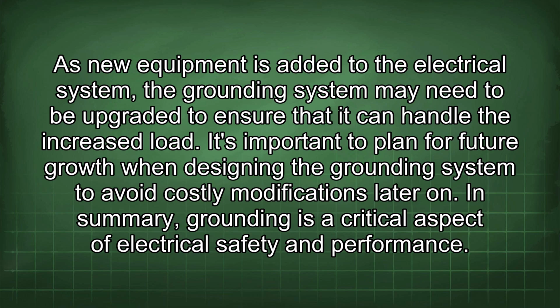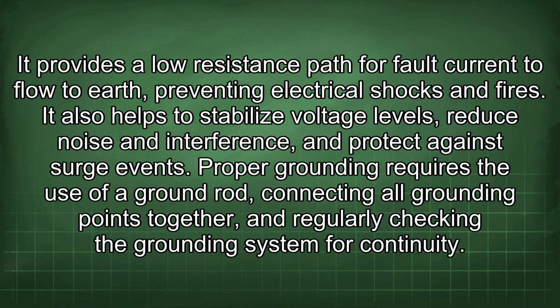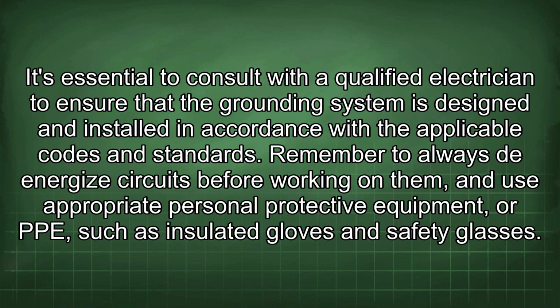In summary, grounding is a critical aspect of electrical safety and performance. It provides a low resistance path for fault current to flow to earth, preventing electrical shocks and fires. It also helps to stabilize voltage levels, reduce noise and interference, and protect against surge events. Proper grounding requires the use of a ground rod, connecting all grounding points together, and regularly checking the grounding system for continuity. It's essential to consult with a qualified electrician to ensure that the grounding system is designed and installed in accordance with the applicable codes and standards.